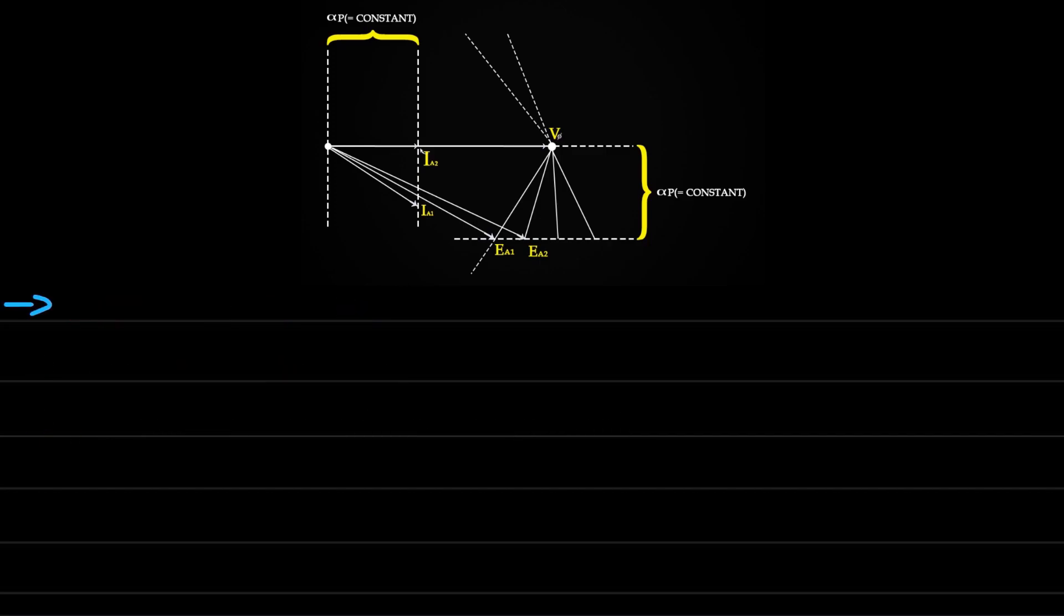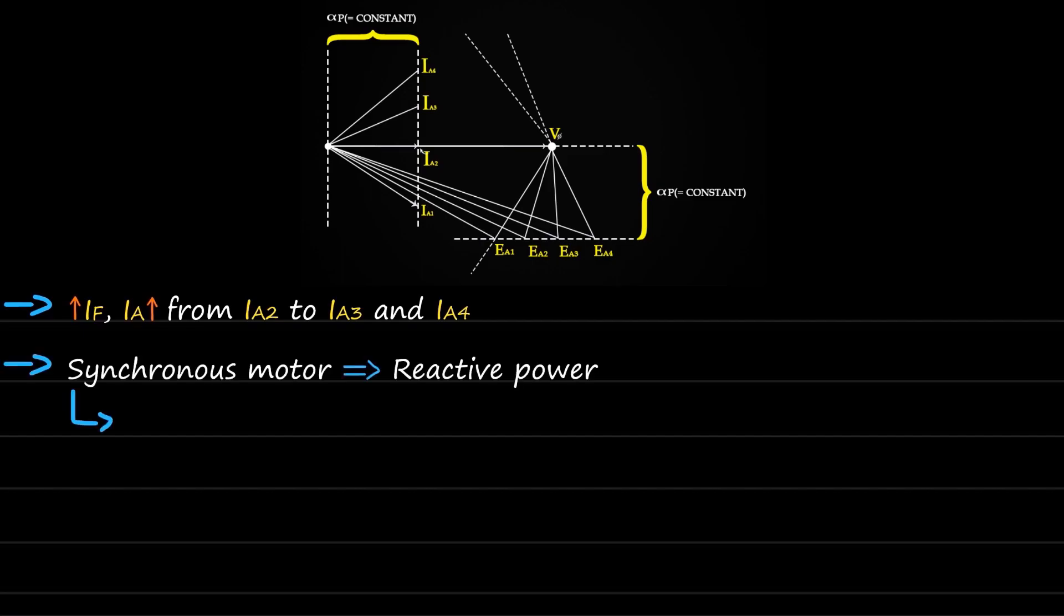Now, what will happen if we keep increasing IF? Value of Ia increases from Ia2 to Ia3 and Ia4, which means that the synchronous motor will now be providing reactive power - that is, the leading operation condition has been achieved.